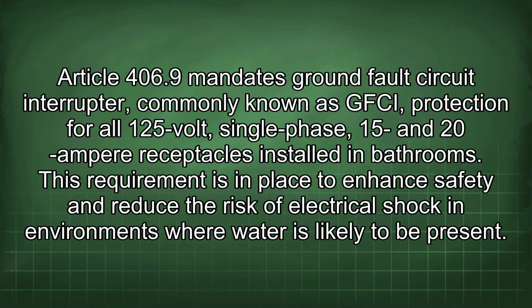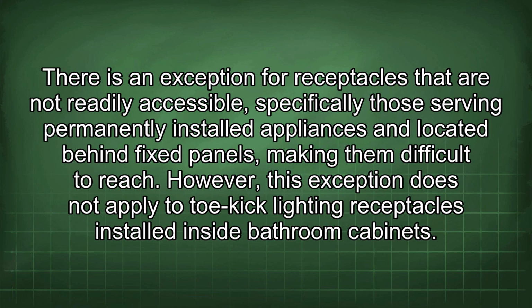Article 406.9 mandates ground fault circuit interrupter, commonly known as GFCI, protection for all 125-volt, single-phase, 15 and 20 ampere receptacles installed in bathrooms. This requirement is in place to enhance safety and reduce the risk of electrical shock in environments where water is likely to be present. There is an exception for receptacles that are not readily accessible, specifically those serving permanently installed appliances and located behind fixed panels, making them difficult to reach.